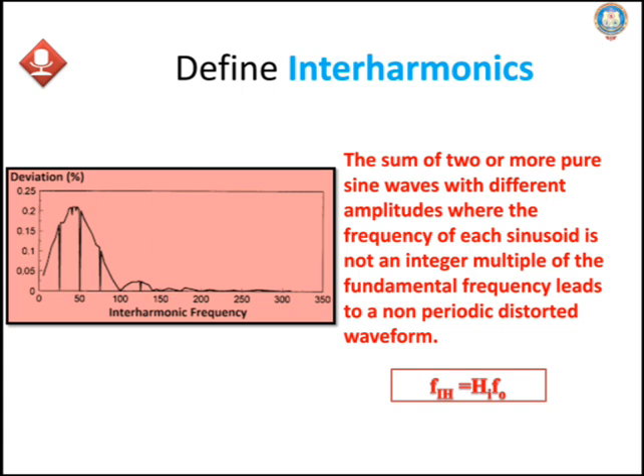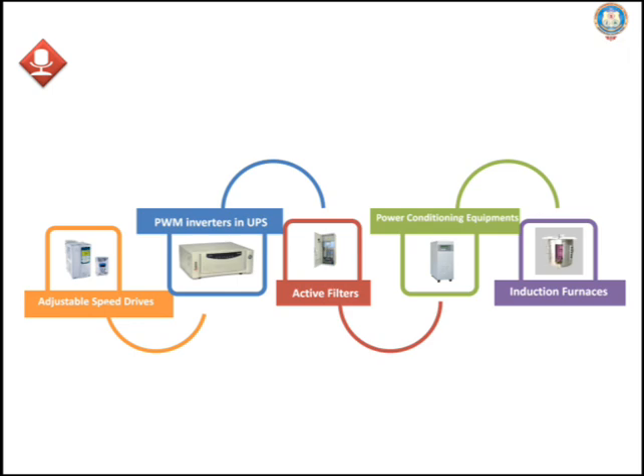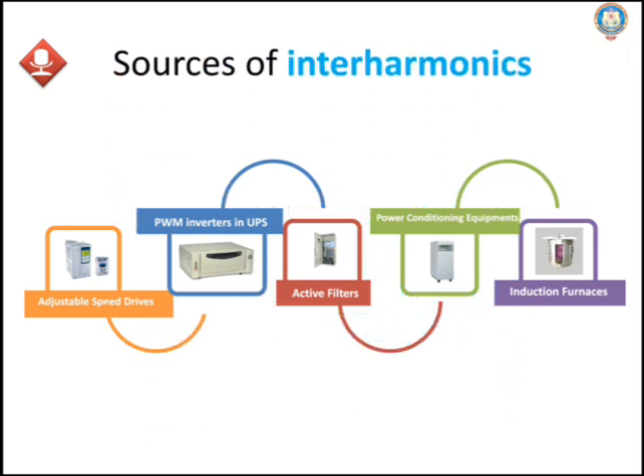The sum of two or more pure sine waves with different amplitudes, where the frequency of each sinusoid is not an integral multiple of the fundamental frequency, will lead to a non-periodic distorted waveform. What are the sources of inter-harmonics? The sources of inter-harmonics are adjustable speed drives, PWM inverters, active filters, power-conditioning equipment, and induction furnaces.